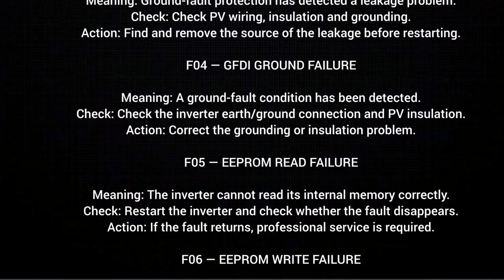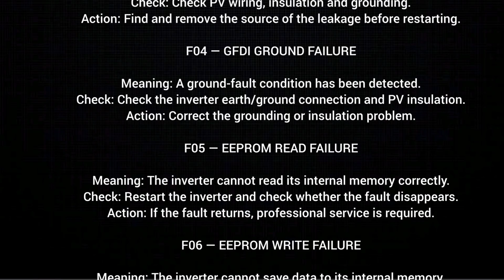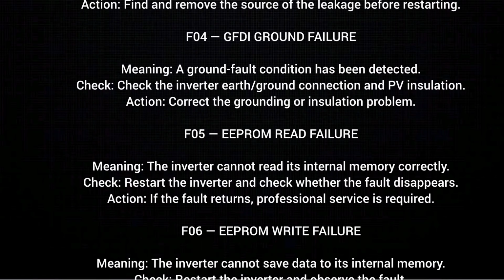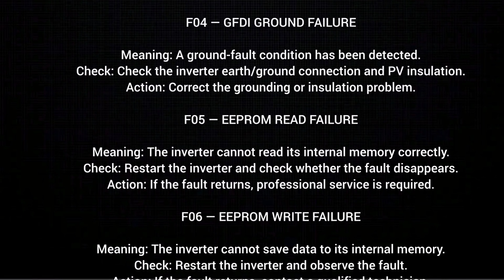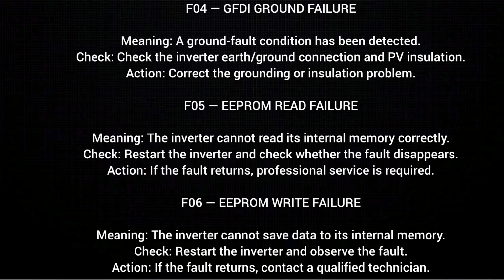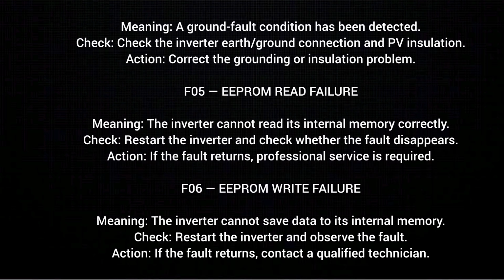F04 GFDI ground failure, meaning a ground fault condition has been detected. Check. Check the inverter earth ground connection and PV insulation. Action. Correct the grounding or insulation problem.